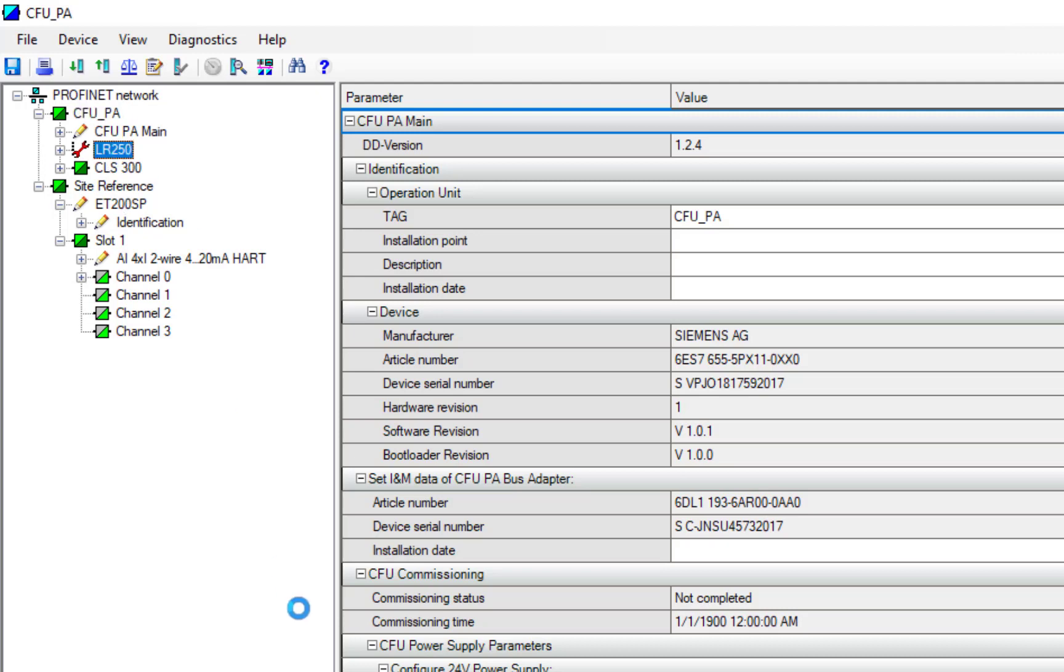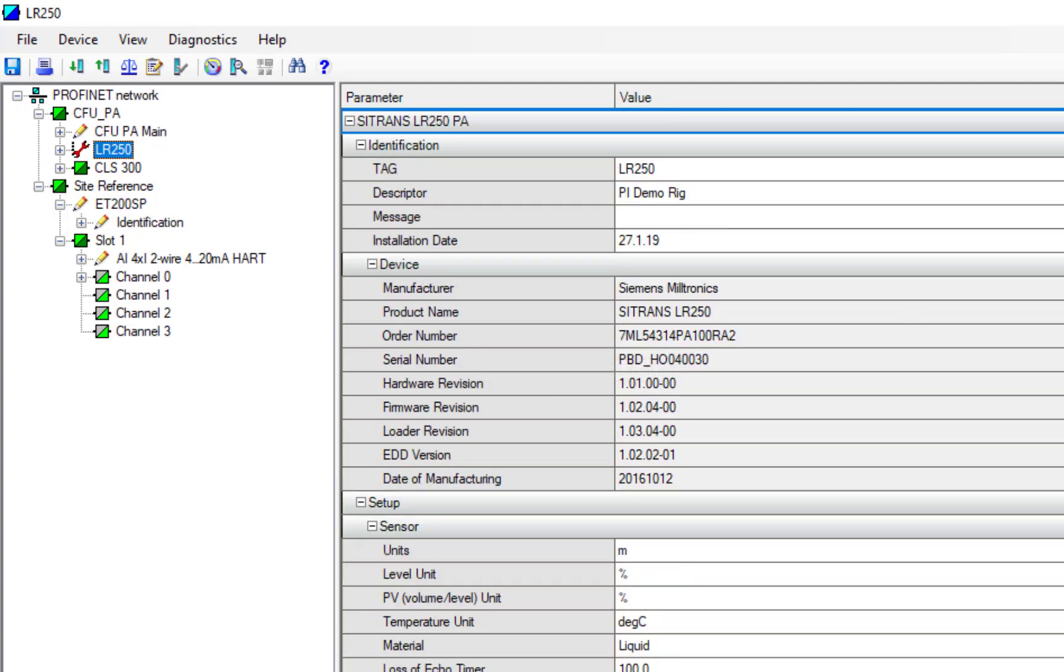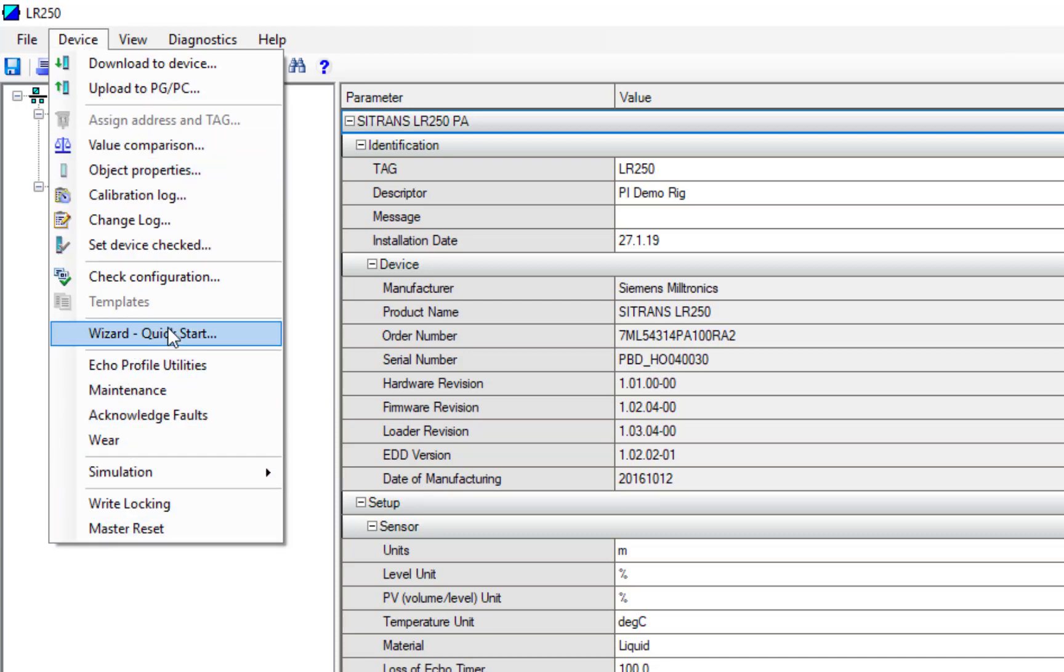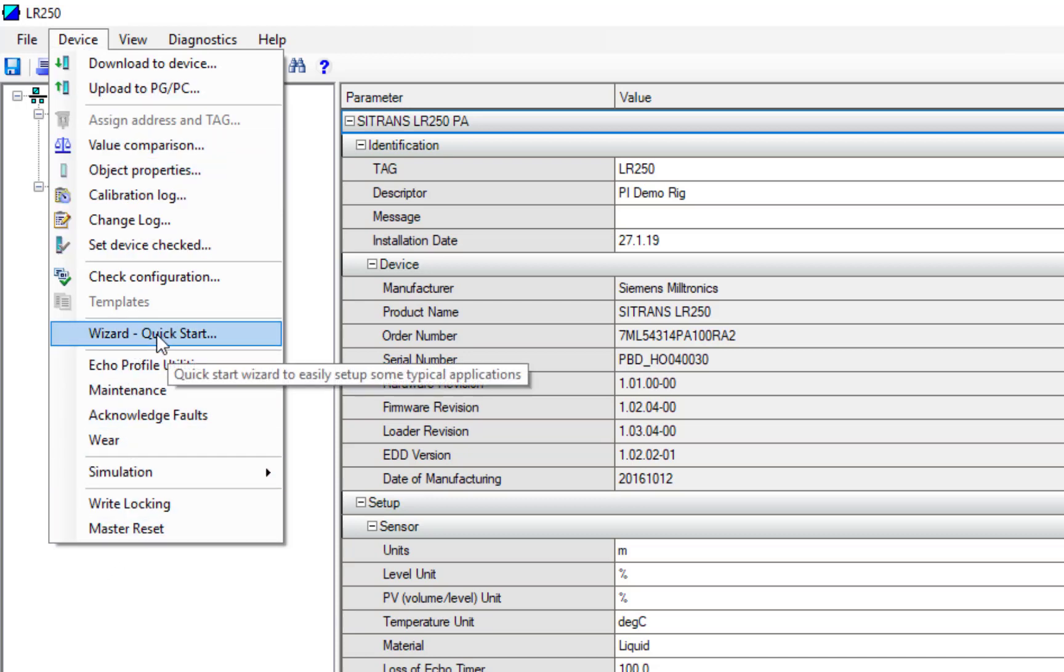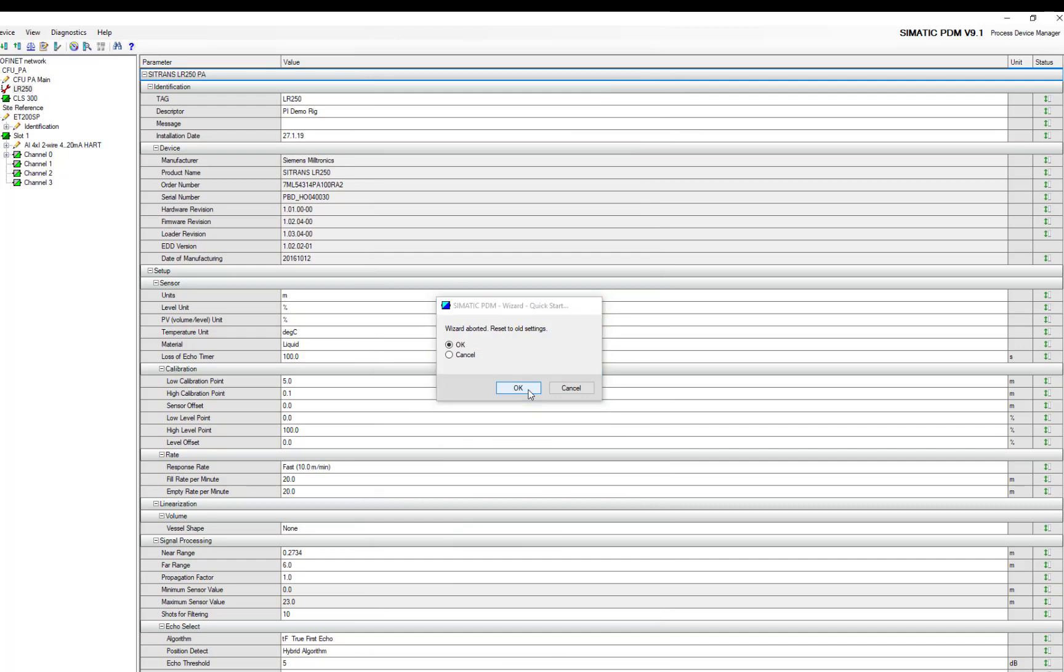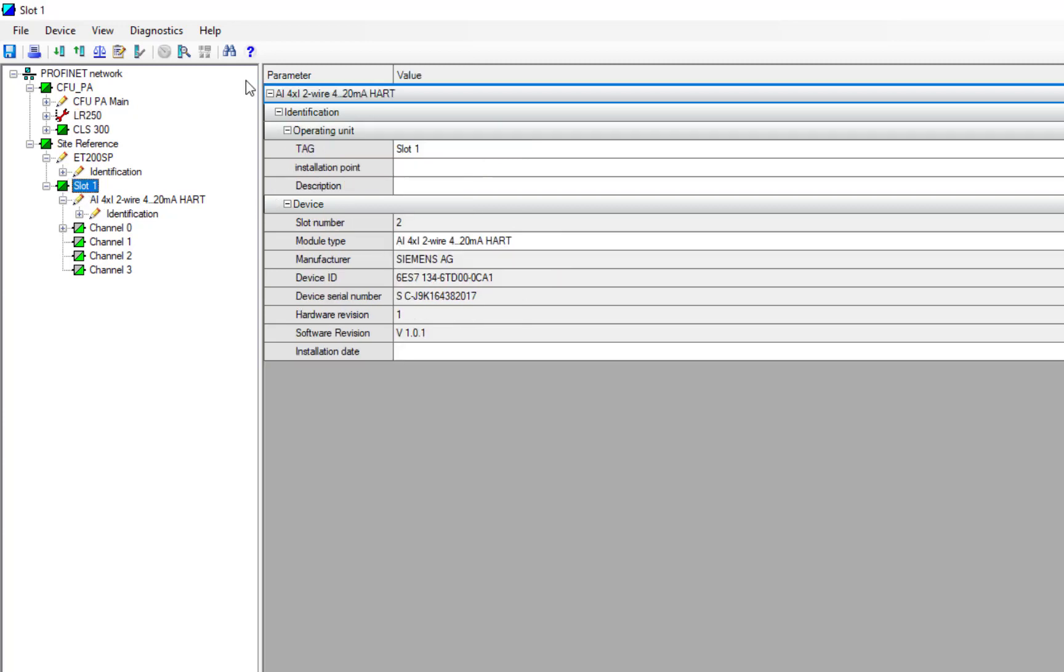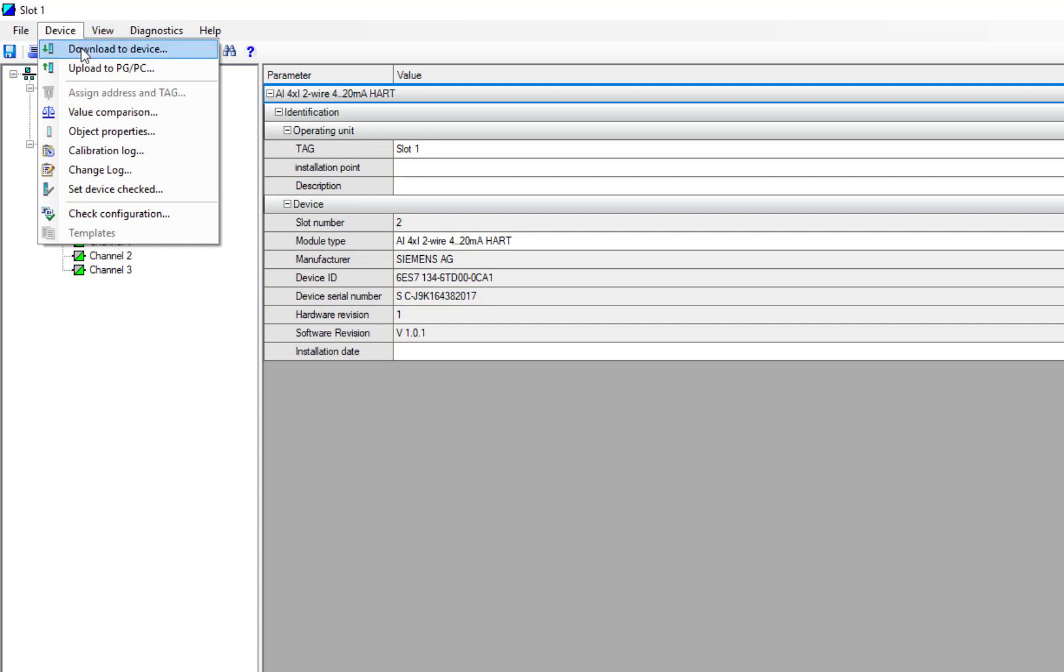As soon as I select the 250, so this is a radar device, it will load the LR250 parameters, and then we'll bring up all of the LR250 menu structures. So have a quick look at things like quick start wizards for configuring the device or echo profiles. What I wanted to show you is some of the diagnostics you get from standard HART or milliamp devices.